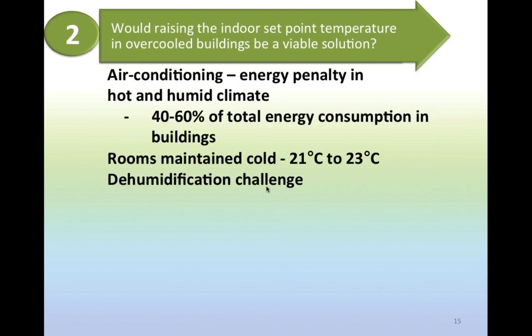Now, I'm going to pose this question here, the second question. Would raising the indoor set point temperature in overcooled buildings be a viable solution? We did a study in our campus probably about 10 years ago, and this slide is just highlighting to you the issues in terms of energy consumption, which is quite true, the high energy penalty I alluded to earlier. Rooms are maintained cold due to the point that I mentioned in terms of addressing the humidity.